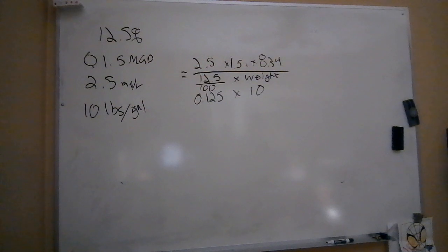2.5 times 1.5 times 8.34, and then I'm going to divide that out by the 0.125 times my 10 pounds per gallon. And that gets me to 25.02, we'll just say 25.0 gallons.